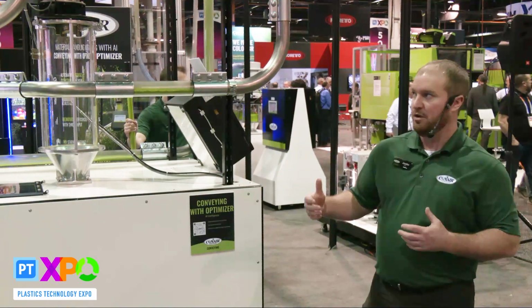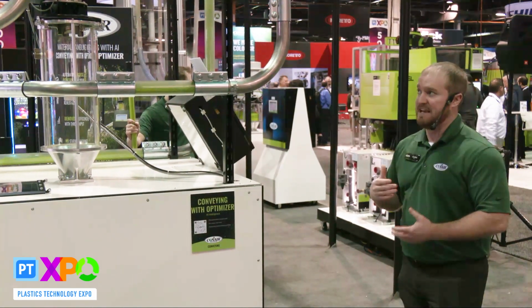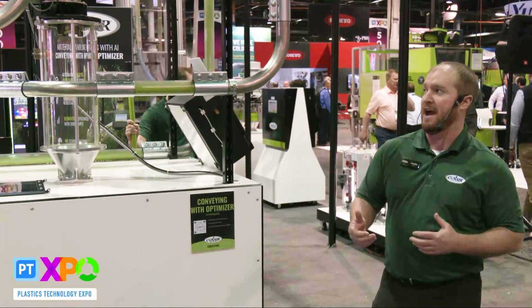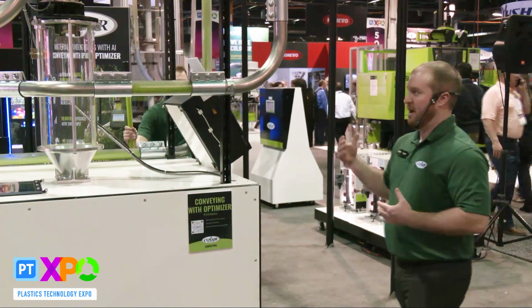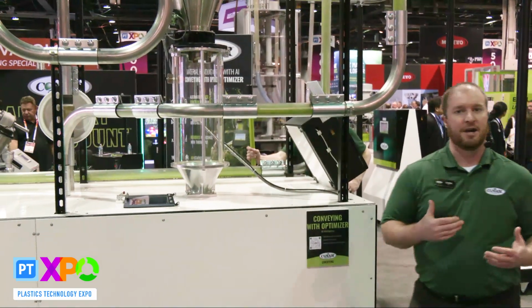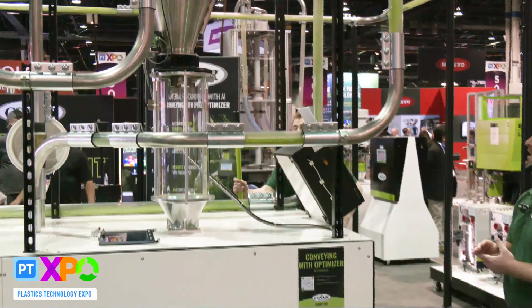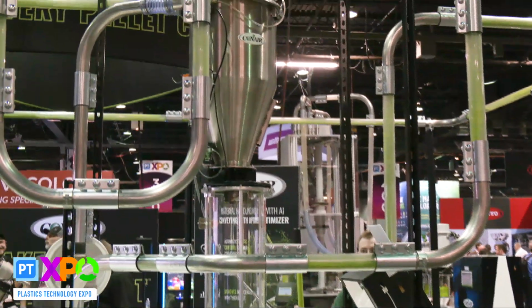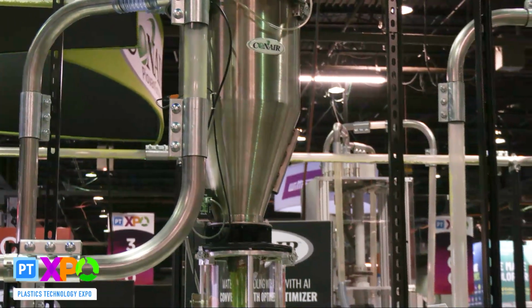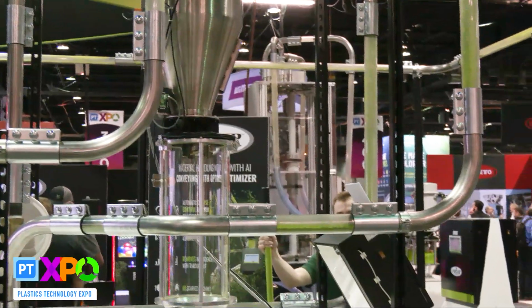In that, we're constantly monitoring the system. We're going to see things that change in real time, and we're going to react to them. So right now, this is a system that's running in a good state. We're conveying material up to the receiver. We feel pretty good about how we're operating. What we're going to do here in a second is induce a vacuum leak in this system, so we're going to see what happens when there is a vacuum leak.